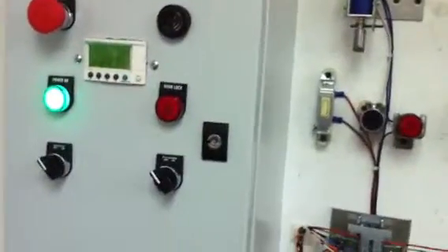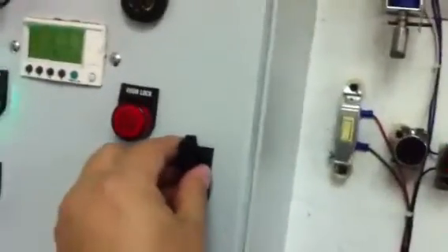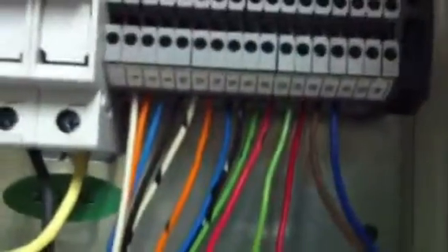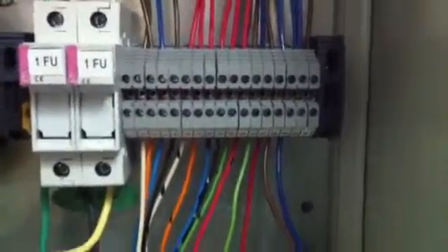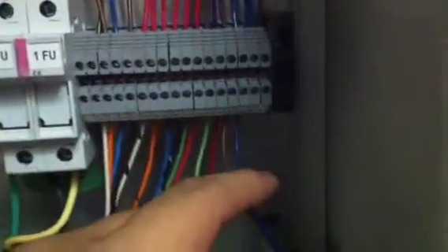Internally, we have some connections to allow you to interact with the system alarm sensors. That's for advanced functions. We have three terminals, 28 and 29, or 32 and 34, which when there's an alarm, those two are coming off. And when it's actually these two down here, when everything is okay, there's voltage over here. So in case of a failure or a fire alarm, this will go down.